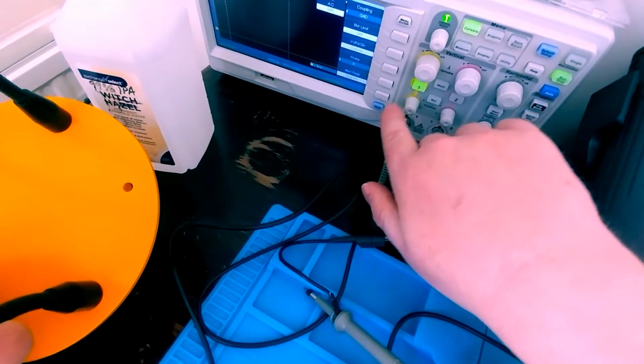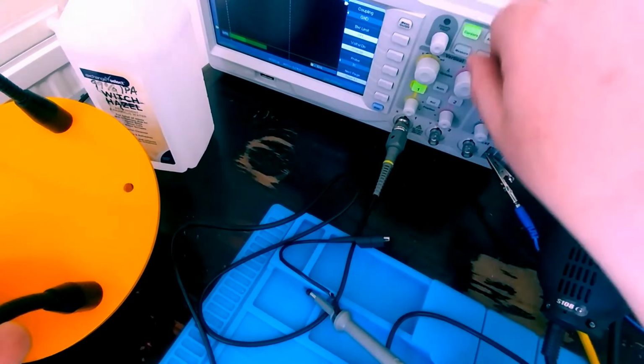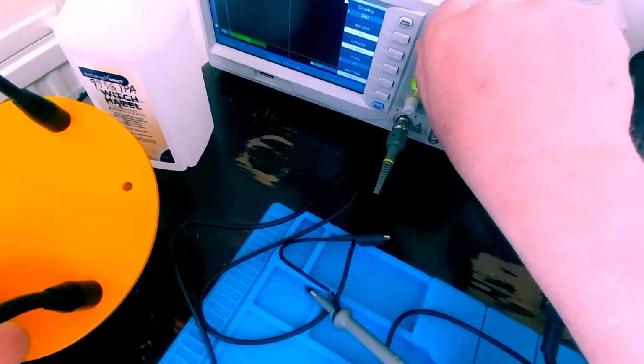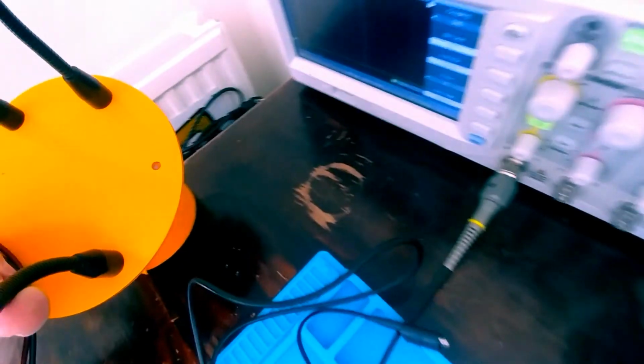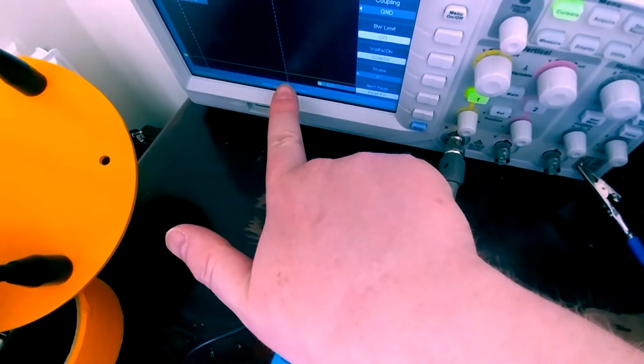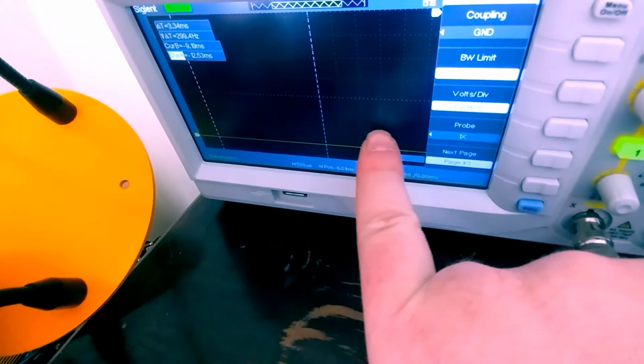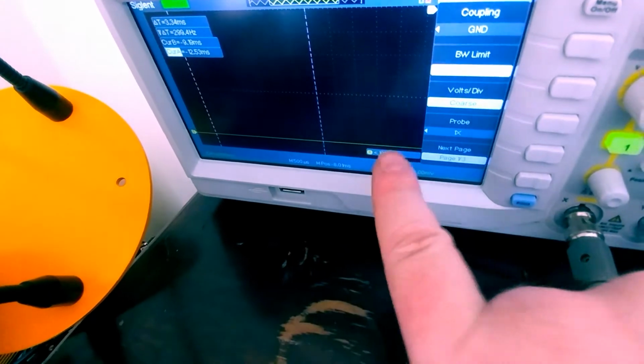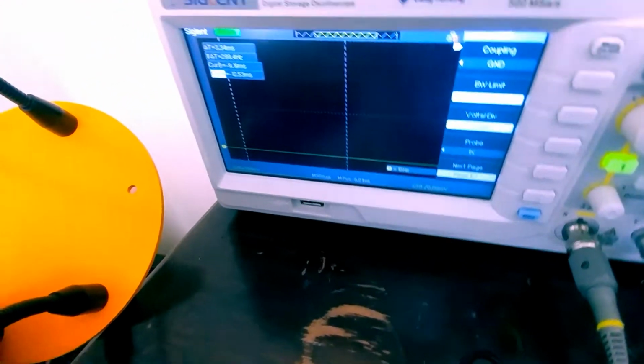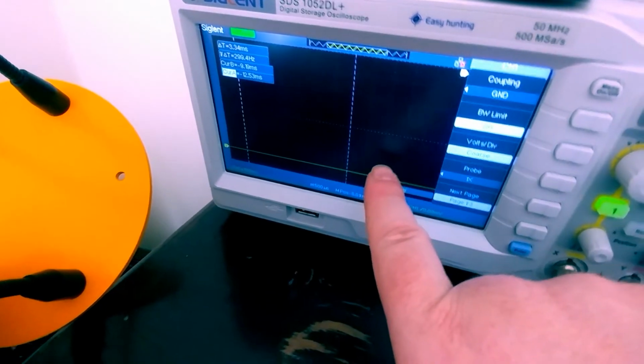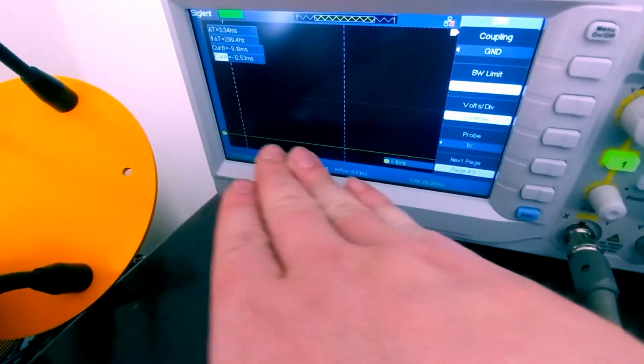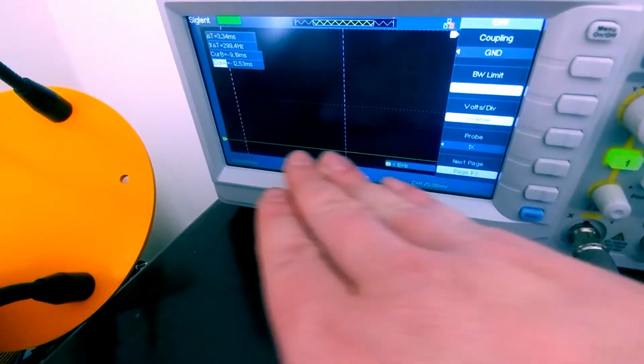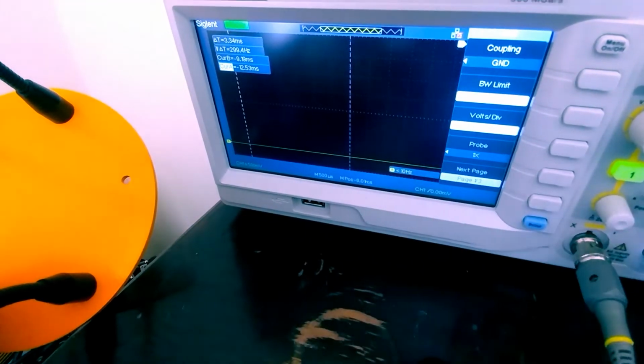And by setting it to ground, then I'm able, oh nope, don't need to adjust intensity, but I guess I should, just in case this is a little bit hard to read. You can see that I have a yellow line across my scope. And probably what you can't really make out, unless I get closer, is you have dotted lines, and basically they fill up this entire section. It makes squares, one through your voltage range, up and down, vertical, and one through the horizontal time range.